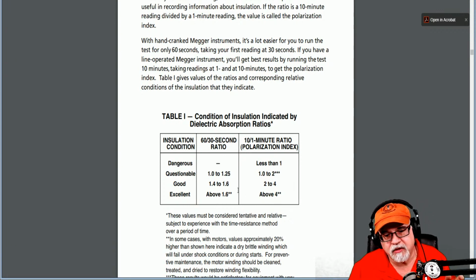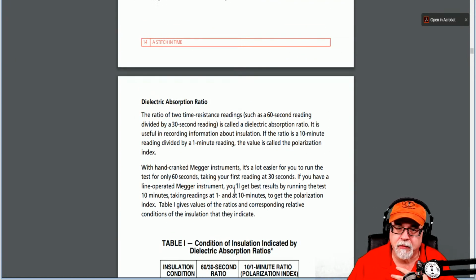Now, that brings me to this. So I've kind of told you all the tests. We recommend the 10 and 1, but I would prefer you to do a full test. Take a reading at 30 seconds, 1 minute, 5 minutes, and 10 minutes. So basically, you're just doing a 10-minute test. That's the best. Dedicate 10 minutes to this test, okay? Don't be in such a hurry.